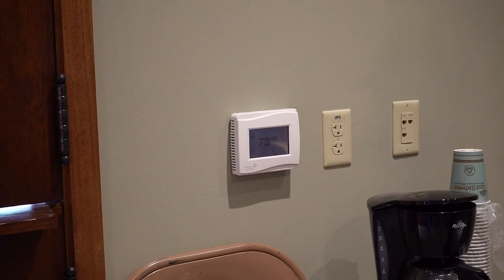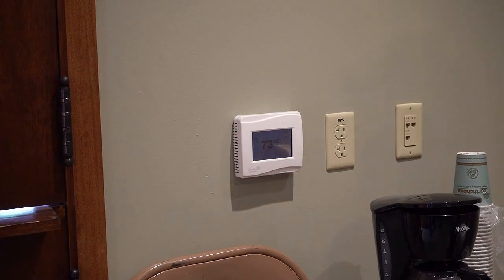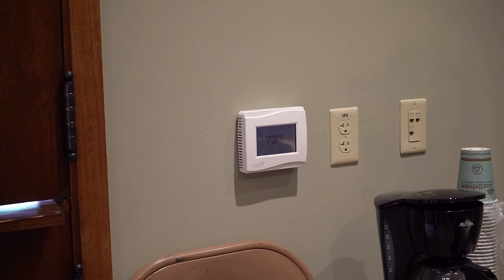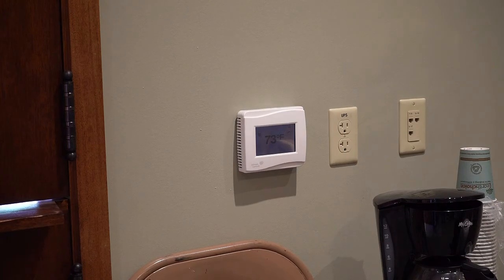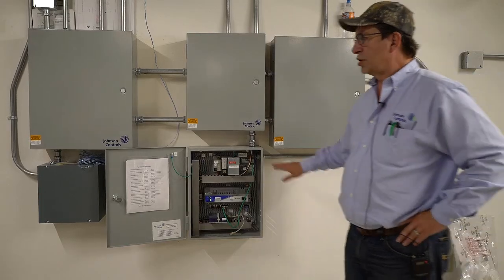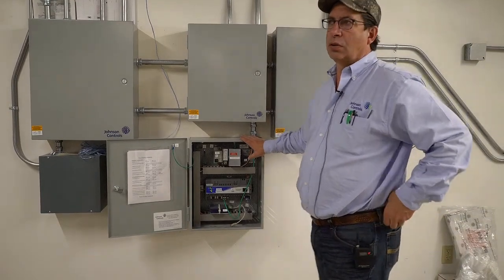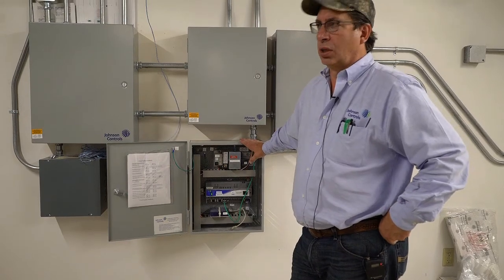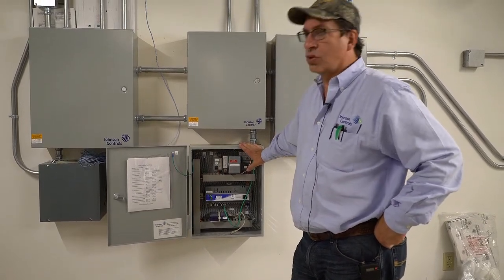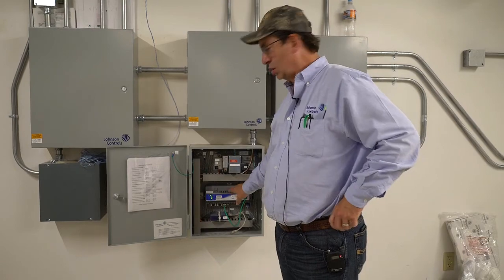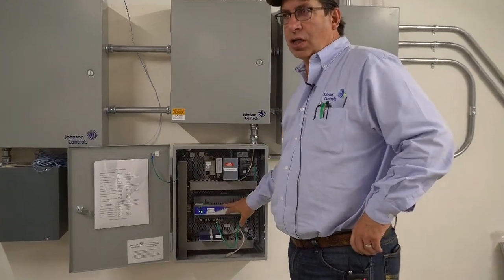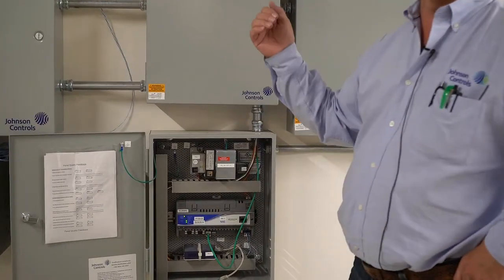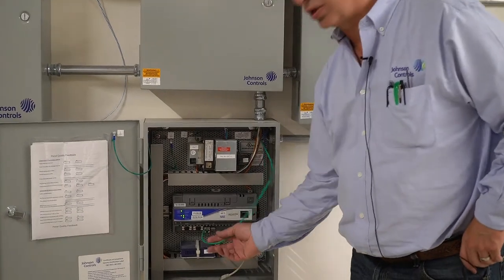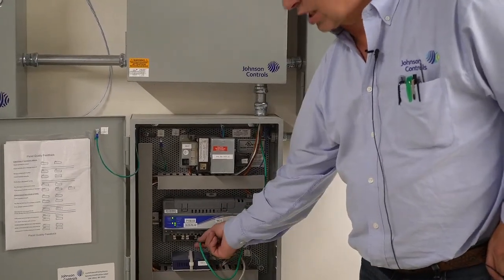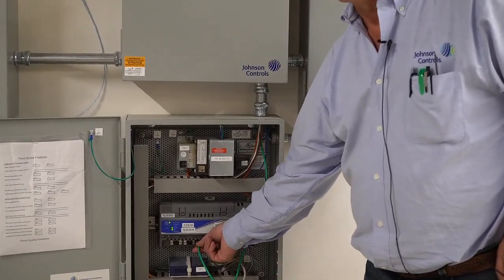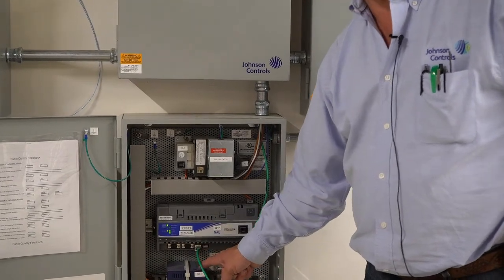There's also an access door around the corner to get up into the ceiling up here to get to equipment above the bathrooms. So this is the NAE for the Mammoth Hotel project. This particular controller, everything else comes to it. We have logic in here. We're able to put this on the trunk, the network, which is your guys' green line here. You'll notice that that's plugged directly into the unit. IT department does not like switches in here.